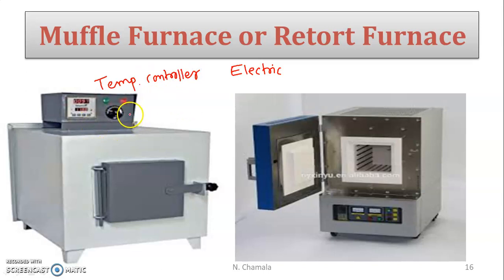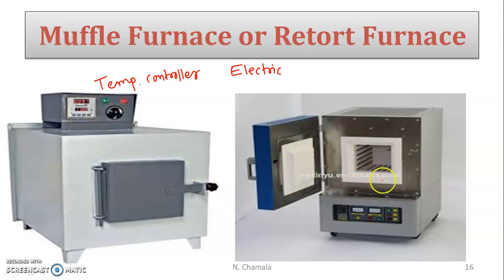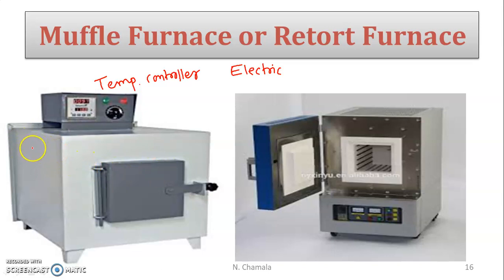In our lab you can see this muffle furnace — the temperature controller is at the top. There is a safety door switch for operator safety. When you open that door, a very small chamber is there — like brick size. At the back side there is a ventilated heating chamber with a small window to pass air.